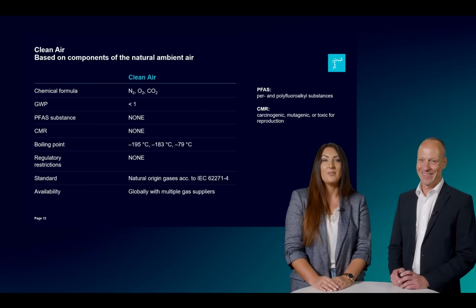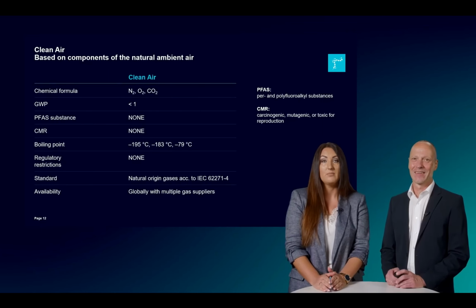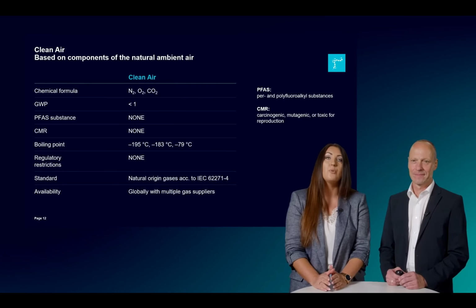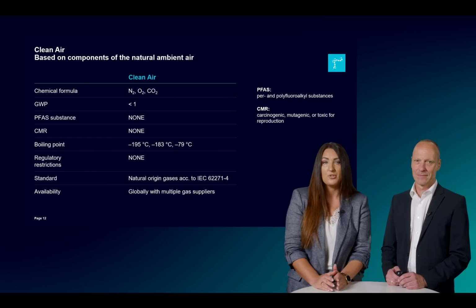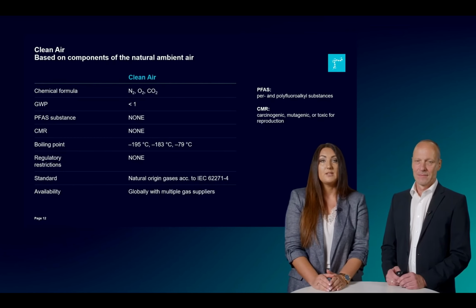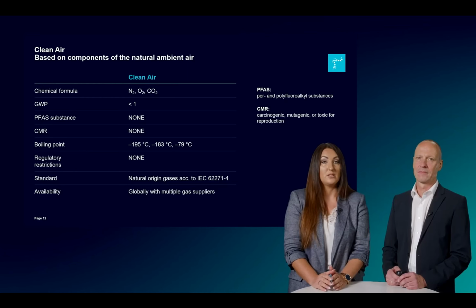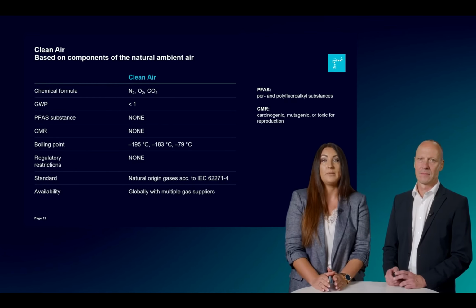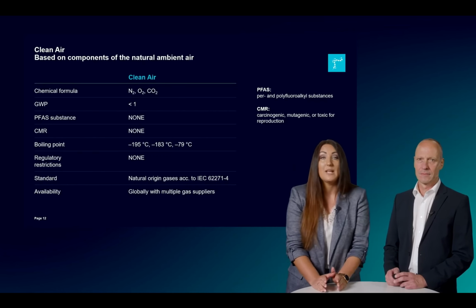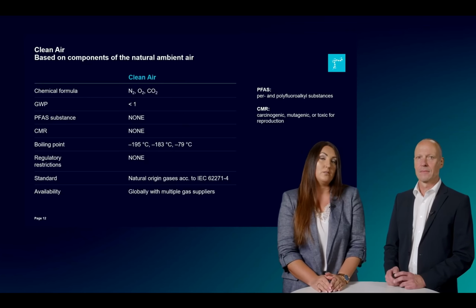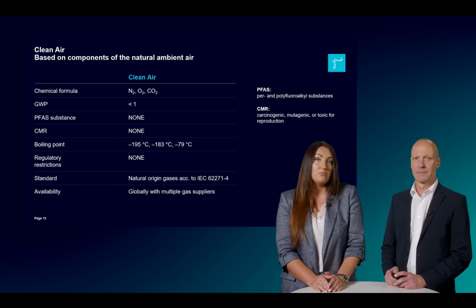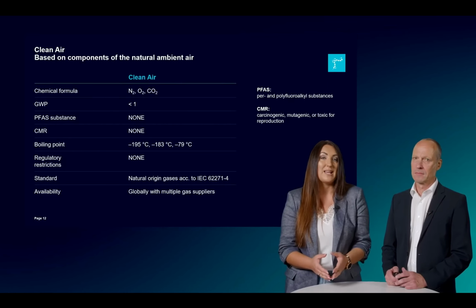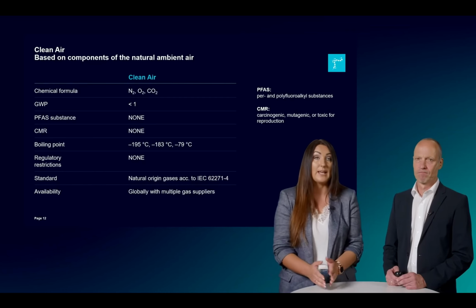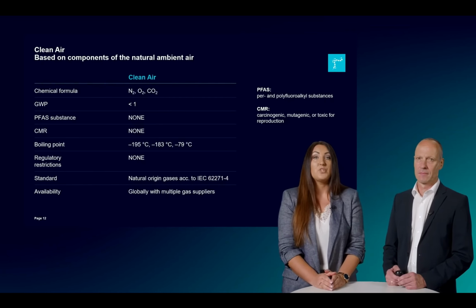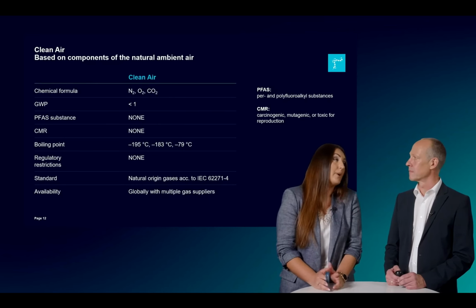For sure. So, clean air. What is clean air? Clean air is an insulating medium which exclusively consists of components of ambient air, such as nitrogen, oxygen, or carbon dioxide. It is free from fluorine compounds, very important, and therefore also extremely safe regarding toxicity, flammability, or material compatibility. With a global warming potential less than 1, it has no impact on our environment. In addition, an installation without fluorine gases has minimum demands when it comes to training for handling the gas mixture, its transport, the switchgear installation, and of course later switchgear operation.